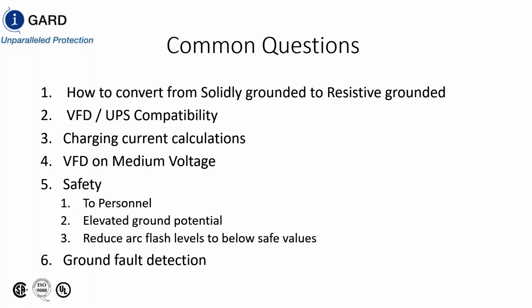Okay, and part of the package that you got was with the resistor monitoring as well, and it just so happens that in Canada, that's now in the code, and if you put in a resistive grounded system, you must have resistor monitoring. Fantastic. Which also, not only does it take care of the open and shorted resistor, but for some reason, they've allowed resistance grounded systems on a distributed neutral network. So if that neutral ever becomes grounded anywhere in the system, you have to isolate the system right away. And we have to look at the conductor between the neutral point of your power source to the resistor. If that becomes open or shorted, we have to isolate the system. Yeah, those are all great things.